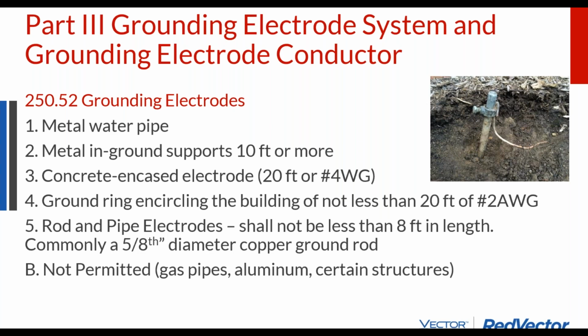The grounding electrode conductor, and I think at this point, in the interest of time, we're just going to do some gotchas in the chart, and that's it, because we're coming up on the 2-hour mark. The main thing is rebar in concrete. You have to have 20 feet of continuous rebar for that rebar to be the ground electrode.